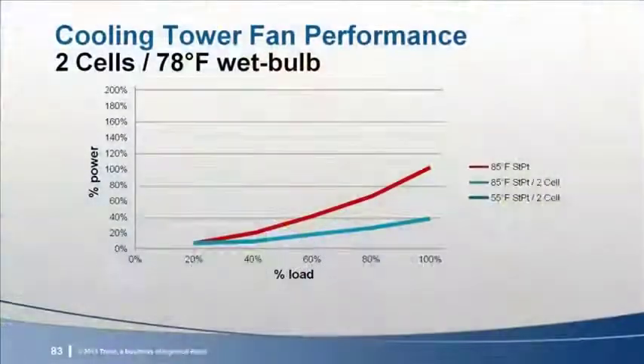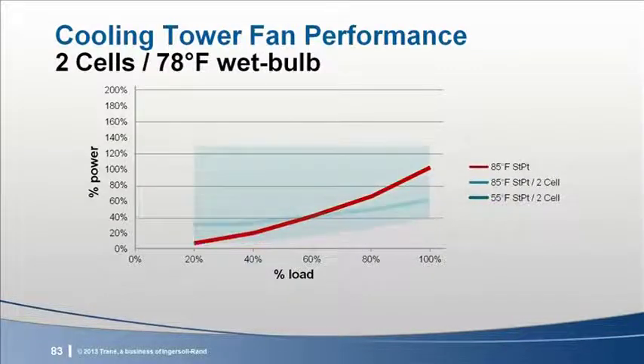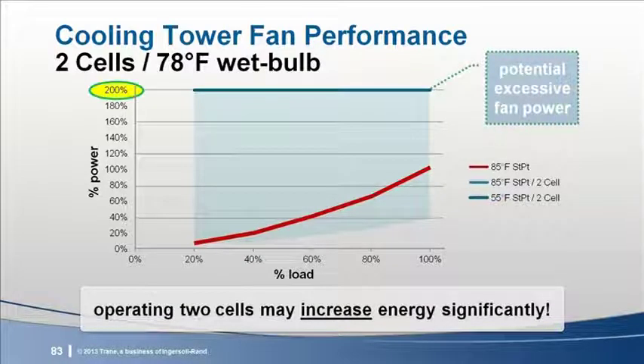The second catch in running additional tower cells is a bit less obvious. Let's look again at the unloading curve. Same slide, but with an added operating line. This line is the power draw of two fans operating at 60 Hertz. As you can see, the total fan power skyrockets to 200% of the original design intent for operation with one chiller. This would happen if the operator manually overrode the fan control set point or drive speed.